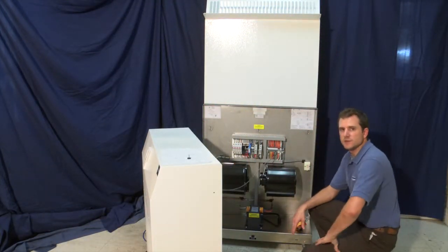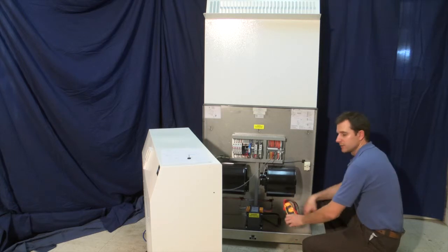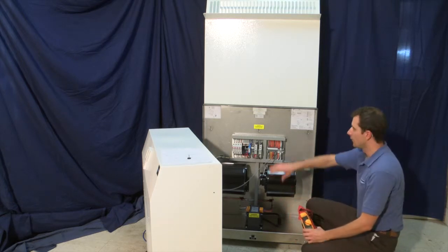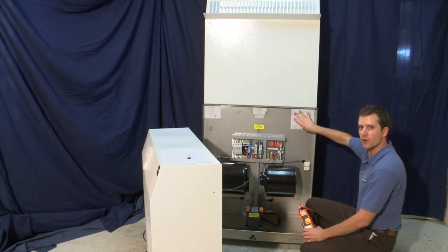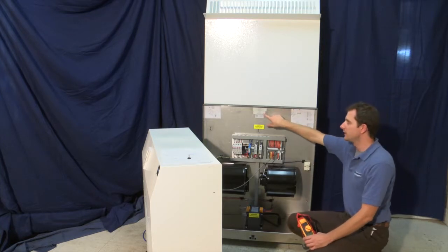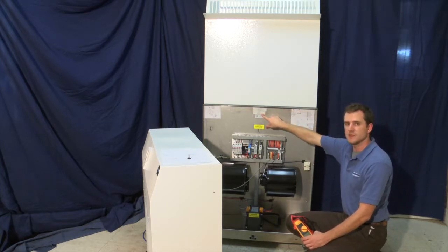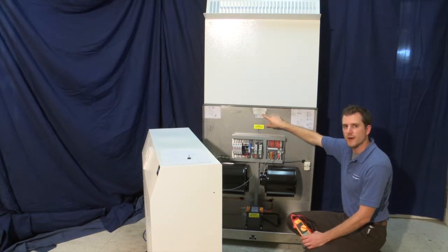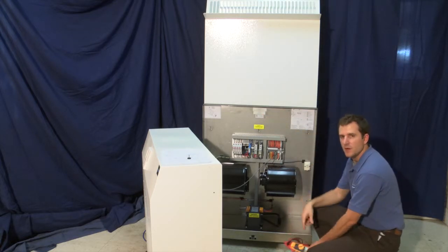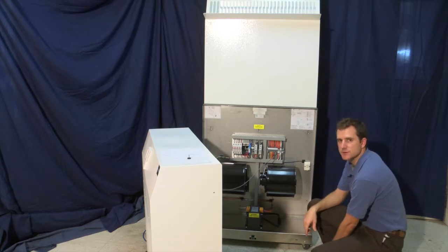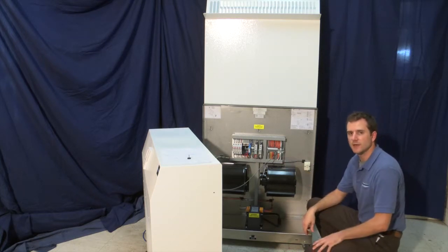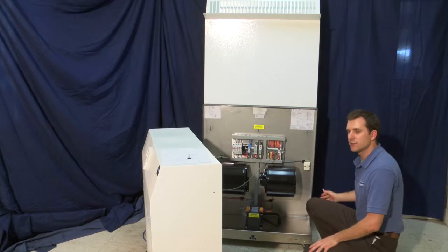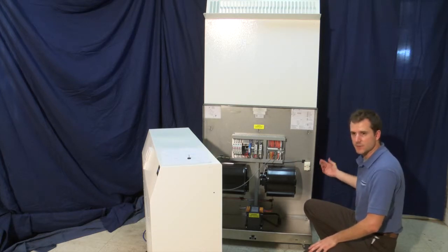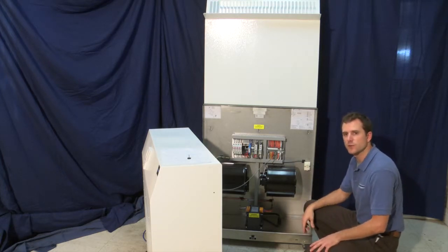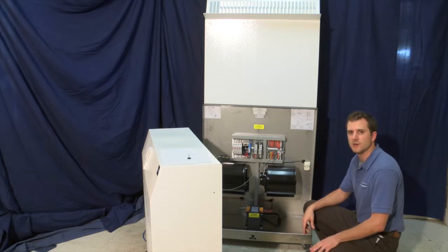The 3 main tools you'll need to troubleshoot a unit are a multimeter or voltmeter, the wiring diagram located on the stainless steel vertical, and the serial number located on the center of the vertical. Humidifirst will not be able to assist in troubleshooting without the unit's serial number. The 3 most common problems encountered are the humidistat is not reading correctly, the unit is not producing humidity or mist, or the unit is overflowing with too much water. Let's look at them one at a time.